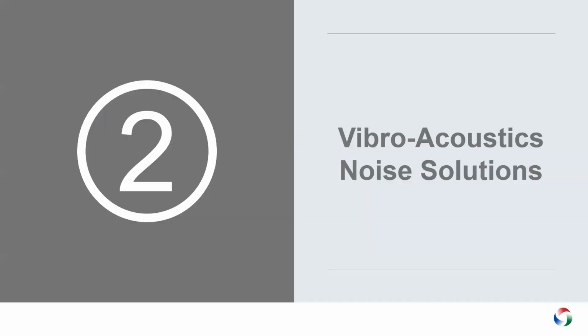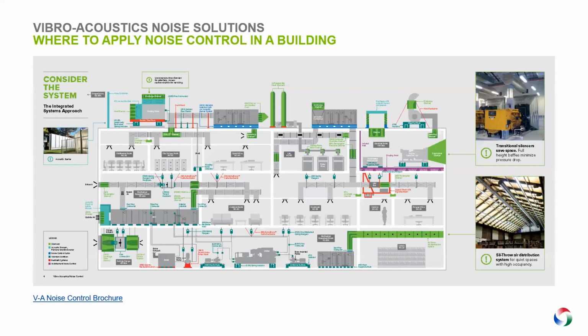The way Vibroacoustics and Long look into noise control is we look into the mechanical drawings from the consultants to see where all the equipment is located, starting from bigger equipment like rooftop units, cooling towers, and chillers, and at the same time smaller equipment like VAV boxes, terminal units, dampers, and diffusers. Based on the location and how the ductwork is running, we do analysis to find out if there will be a noise issue down the road once the building is completed.